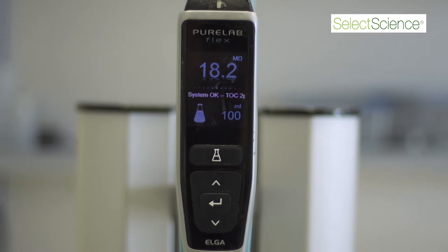With this type of instrument I need ultra-pure water as the mobile phase. In this case I need a very low value of TOC because I analyze organic compounds, and this is very important to obtain low noise in the signal.